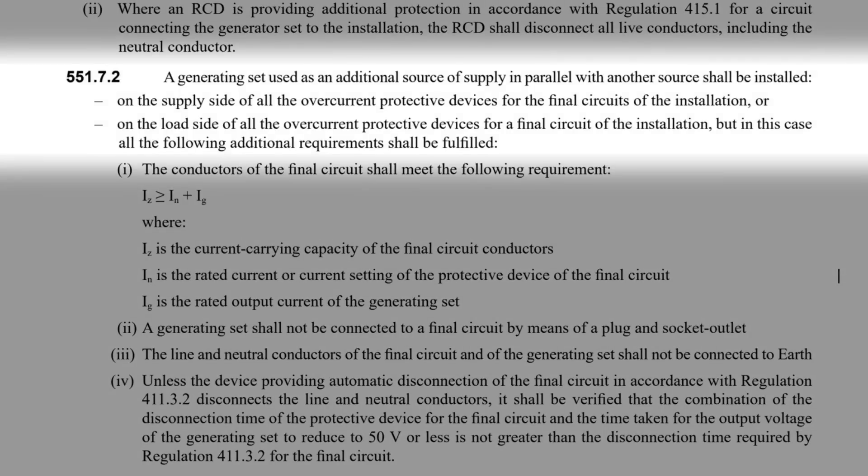The regulation states: a generating set used as an additional source of supply in parallel with another source shall be installed on the supply side of all the overcurrent protective devices for the final circuits of the installation, or on the load side of all the overcurrent protective devices for a final circuit of the installation — but in this case all the following additional requirements shall be fulfilled. So unless you're completely off grid, this regulation describes how PV systems connect into the fixed wiring system of a property.